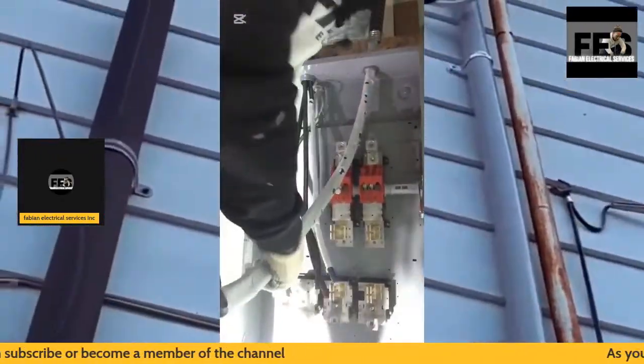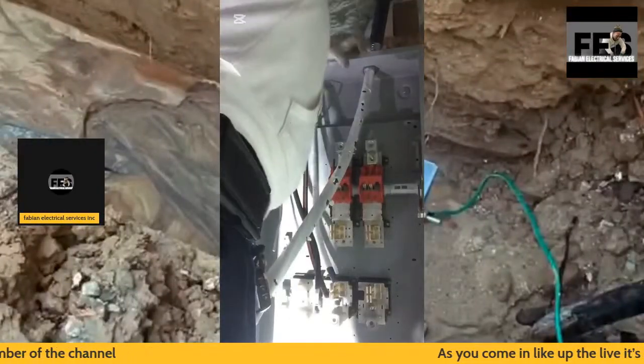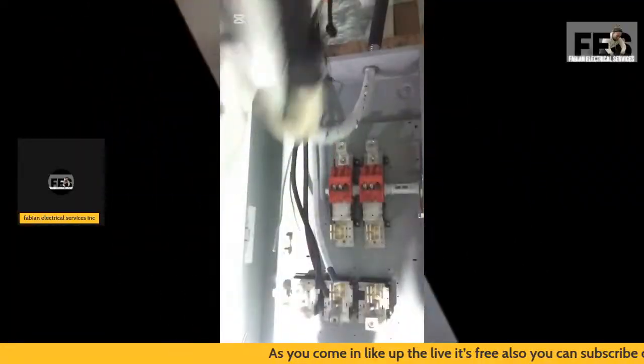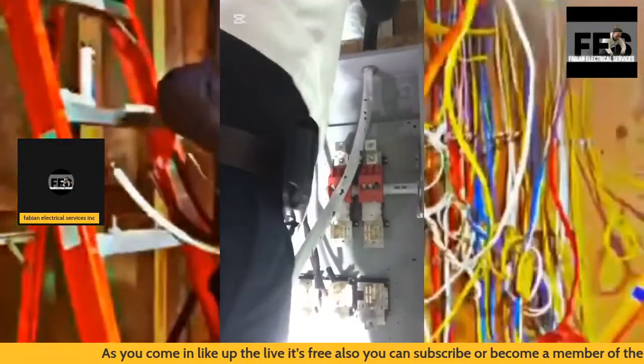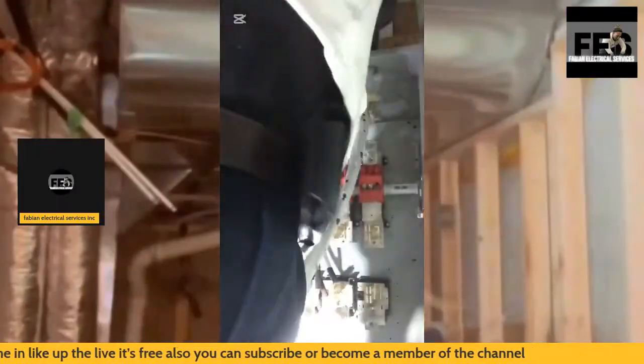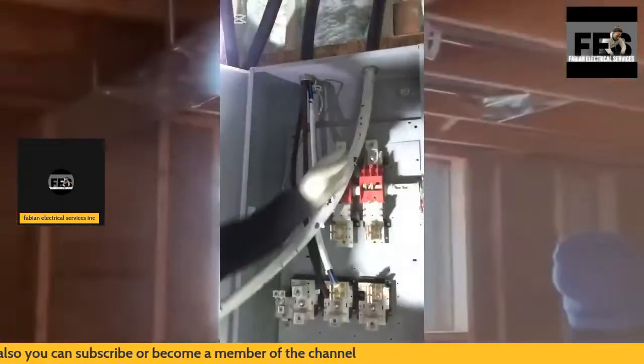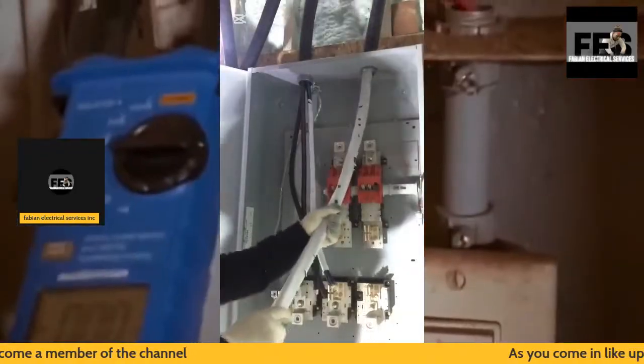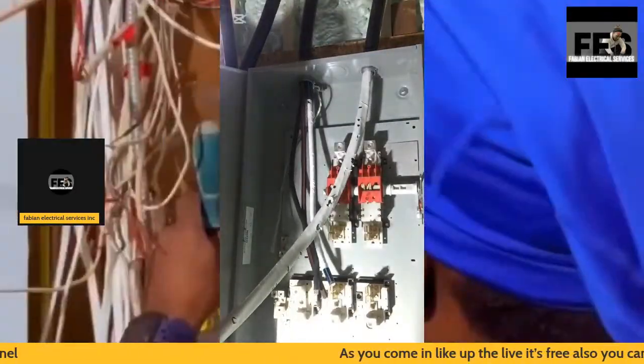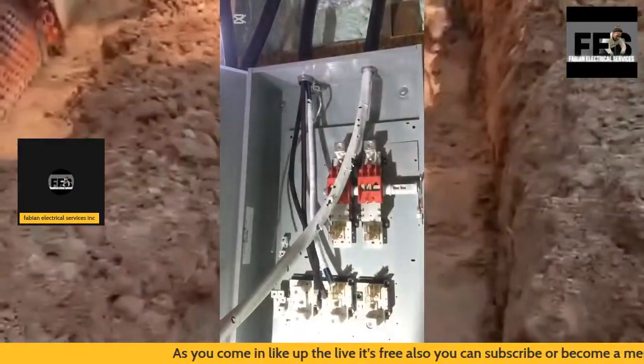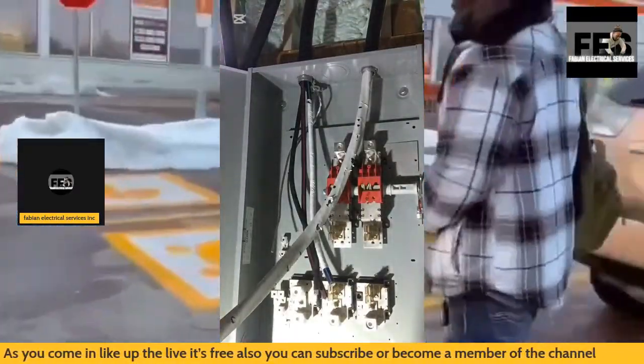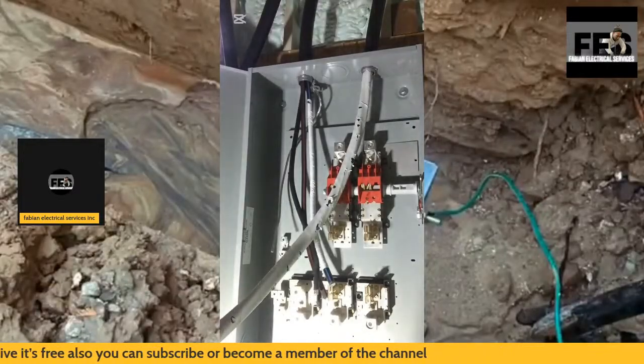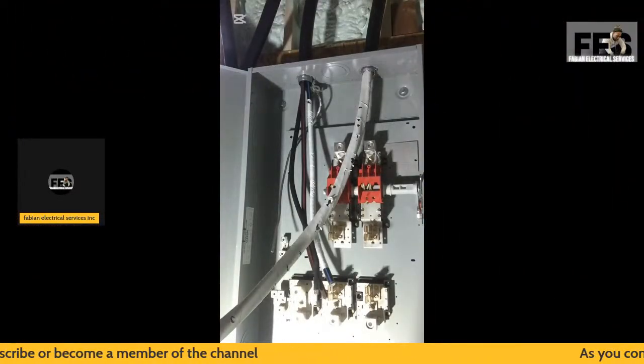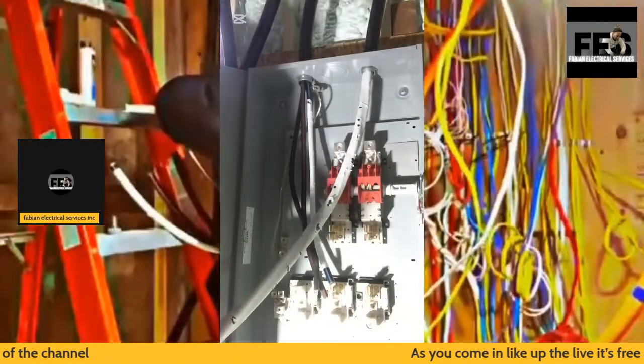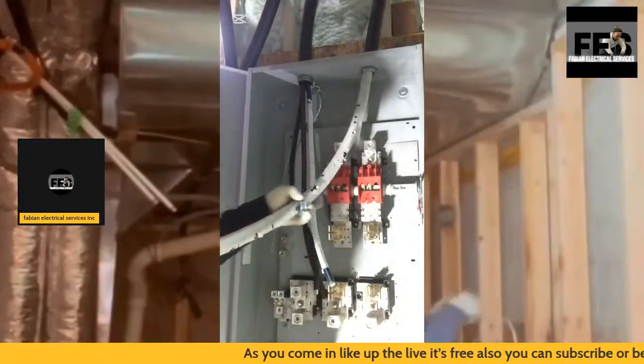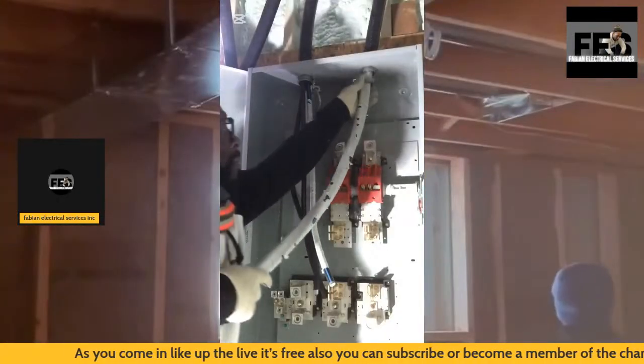Again, the cable, the electrical conduit that I'm using, is going to be the AC conductor. We call it TECK cable, and there are parallel runs being run from the outdoor meter base. What I like to do with an installation like this is keep that white sheeting on. Once I land my conductors inside of the panel, I'm going to remove that white sheeting. I also make sure to put my ground bushing on first.